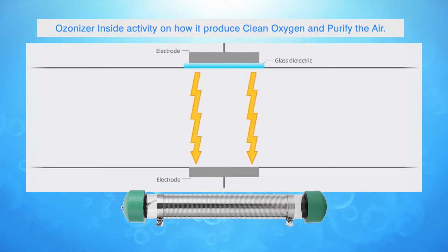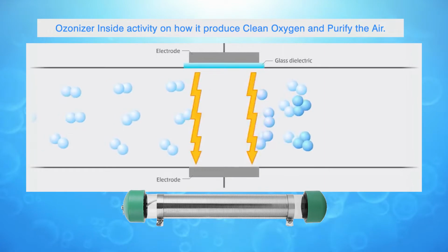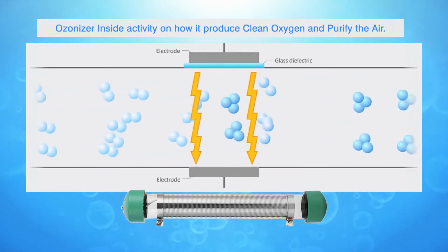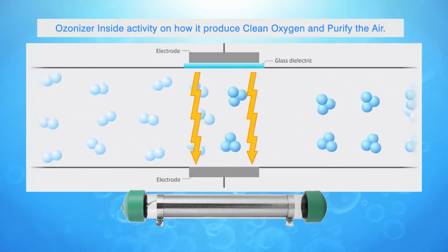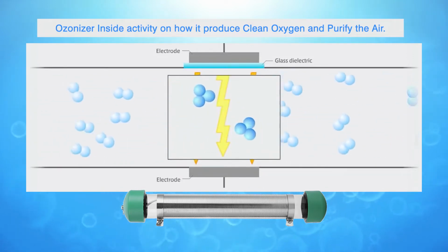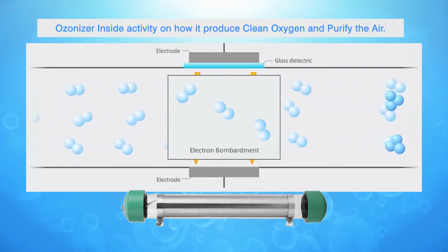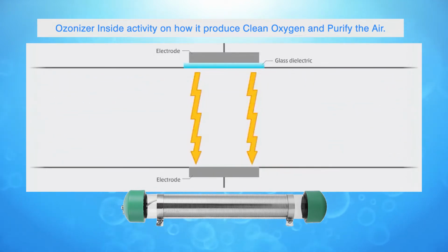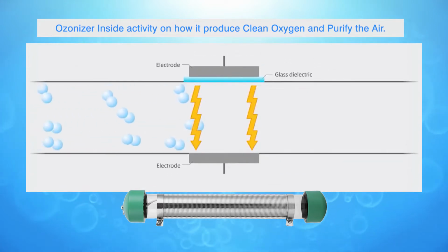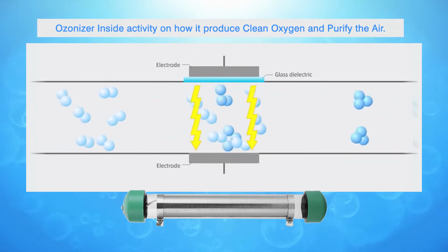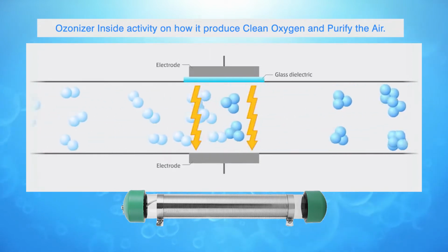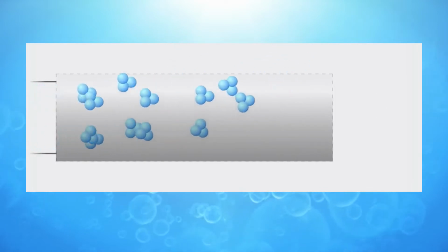Ozone is generated by the silent electrical discharge method. This creates ozone by bombarding oxygen molecules with electrons. In conventional systems, some of the ozone created is broken down by electron bombardment. Research at Mitsubishi Electric has led to a reduction of the discharge gap, which minimizes the breakdown of ozone within the generator. Our ozone generators produce high concentration ozone at low operating costs.